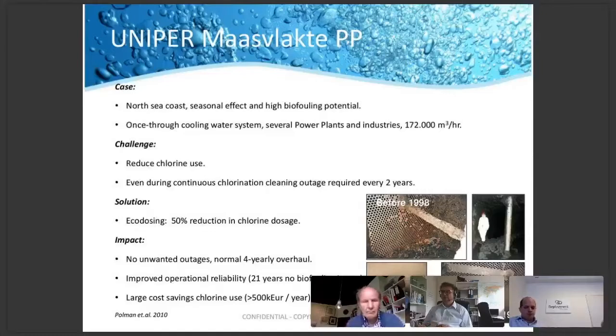The effect of using half the amount of chlorine is shown in the pictures. You can see the pictures from 1999 onwards are spotless clean systems. And the reason for this is that continuous dosing has proven not to be as efficient as Ecodosing, a low intermittent dosing regime, based on the reactional behavior of the local biofouling species.